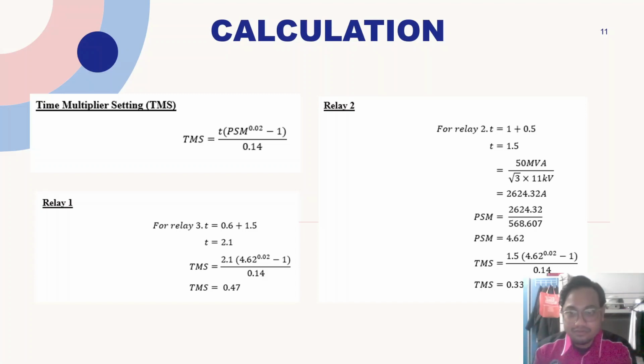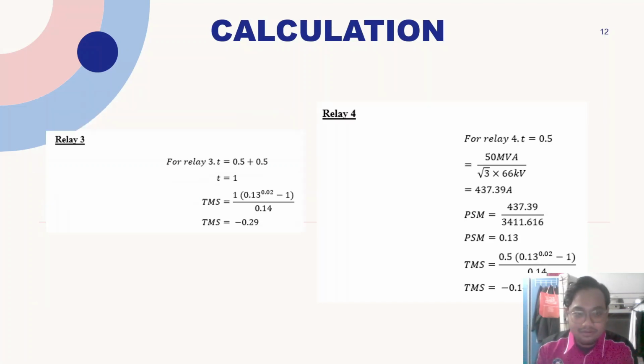For relay 2, we set the timer to 1.5 and the TMS we got is 0.33. For relay 3, the timer we set is 1 second and the TMS is negative 0.29. And the last is relay 4: the timer we set is 0.5 and the TMS is negative 0.13.